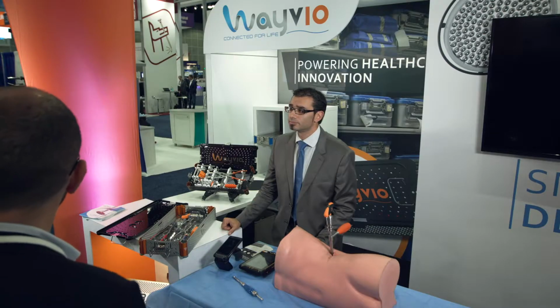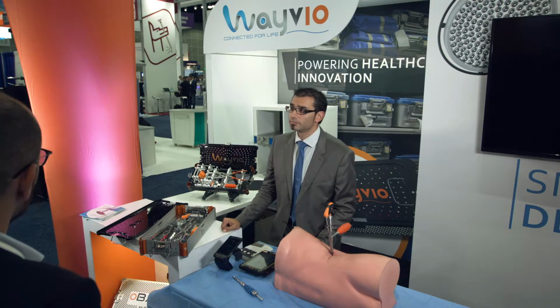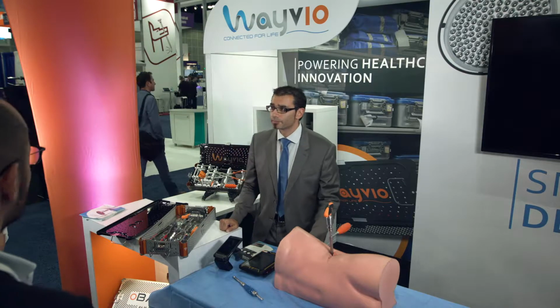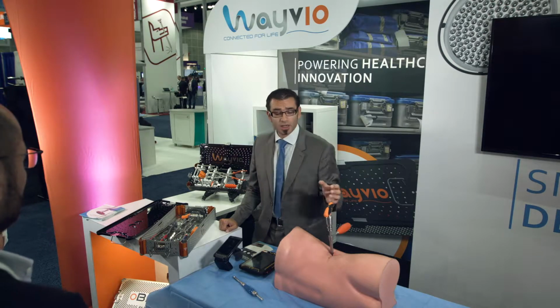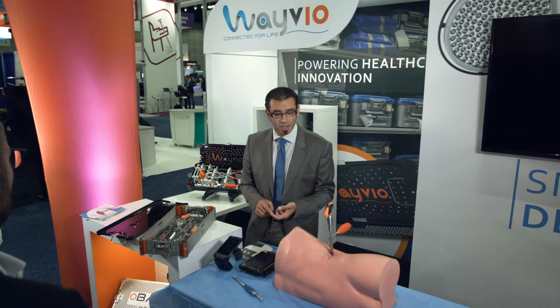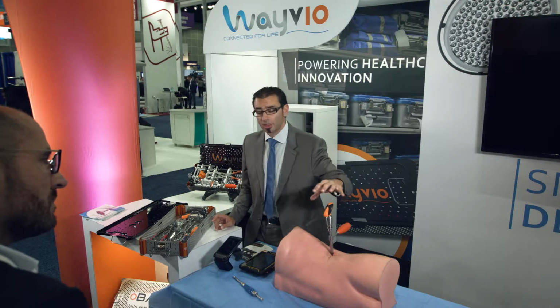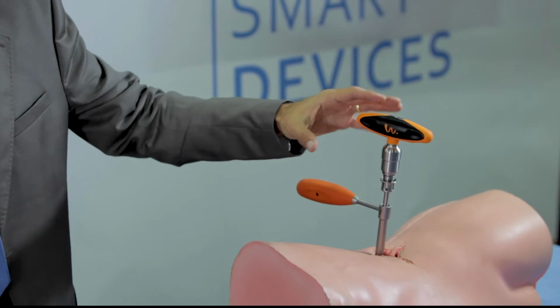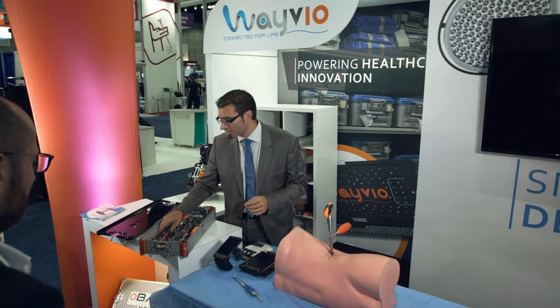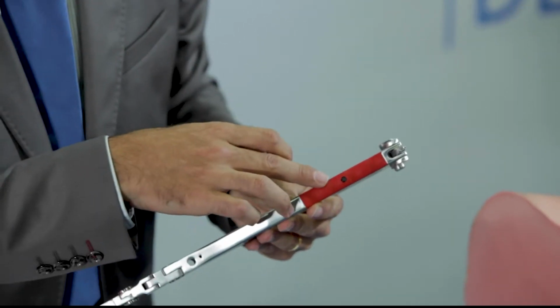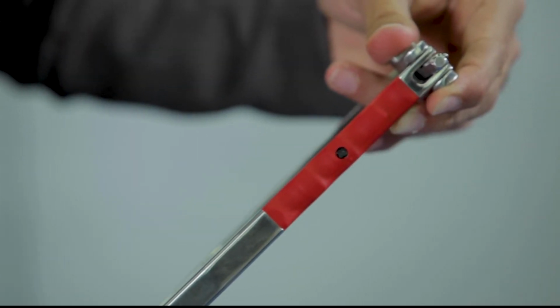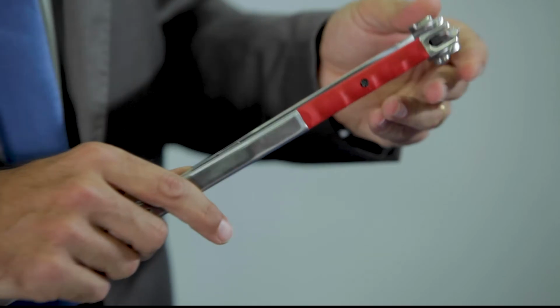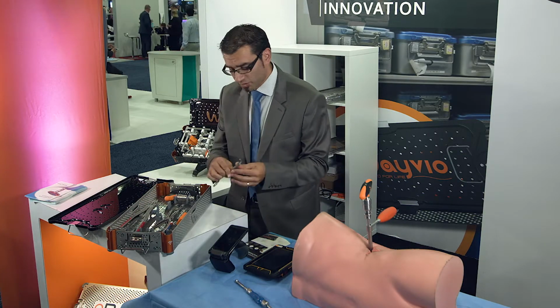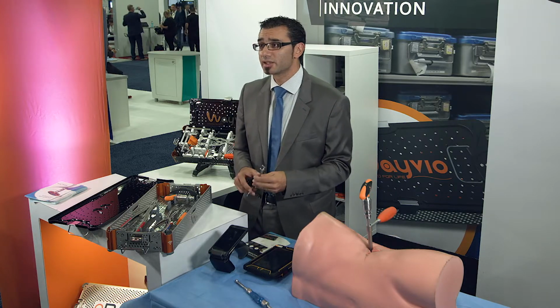So the smart instruments, I'm looking, they're overmolded for the torque limiting device. Do all the instruments need to be overmolded? And if not, what system do you use to be able to track, like the UDI or lot number? Yeah, so for smart devices, as we need a battery and an electronic chip with some electronics, we need a little space to do that. So those smart instruments would definitely be overmolded. But for identification and tracking only, we will be able to integrate little UHF chips that are as tiny as you can see here. Whether on a thin amount of silicone or glued directly to some metallic parts, we would be able to have 100% of the instruments in the case at least equipped with an identification tag.